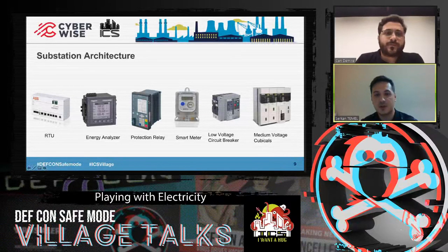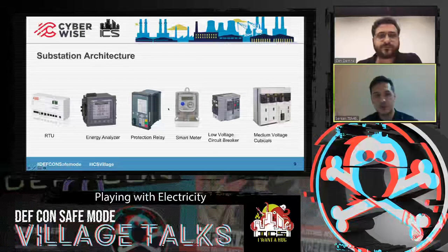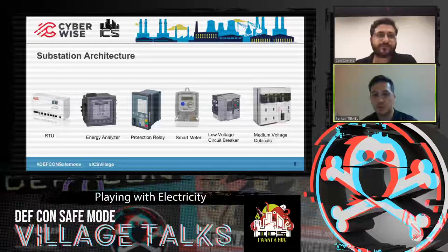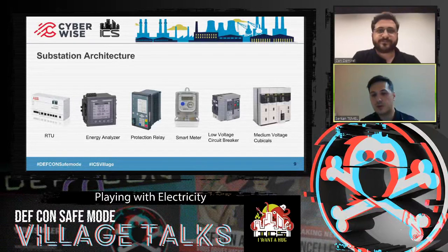For that reason, protection relay is the most critical device in the distribution systems. As mentioned, from a cybersecurity perspective, if you want to shut down the electricity, you have to control the protection relay. Maybe you can attack the RTU, maybe attack the SCADA systems, but it just blocks our monitoring from the field site. But if we want to control the electricity, shut down the electricity, or re-energize the electricity, you have to control the protection relay. The fourth device is the smart meter.